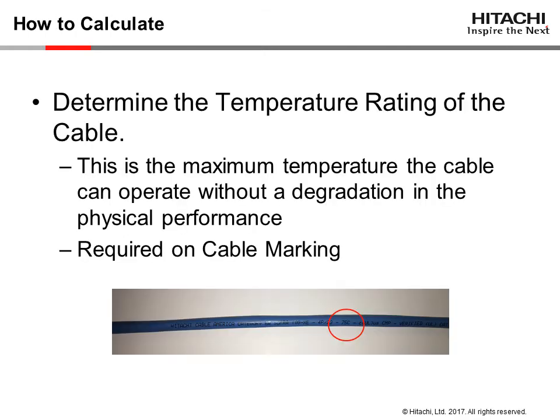The maximum operating temperature of the cable is defined by the cable manufacturer. This defines the temperature above which the cable will degrade and no longer perform. It is required that this temperature be indicated in the cable markings, as seen in the picture below.